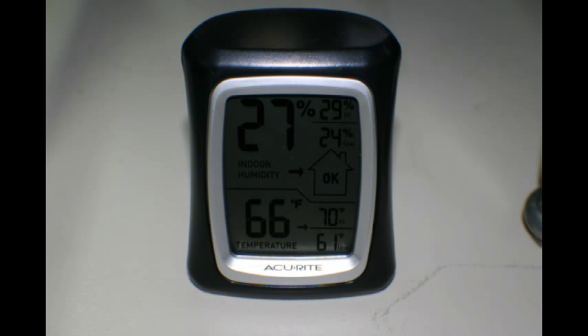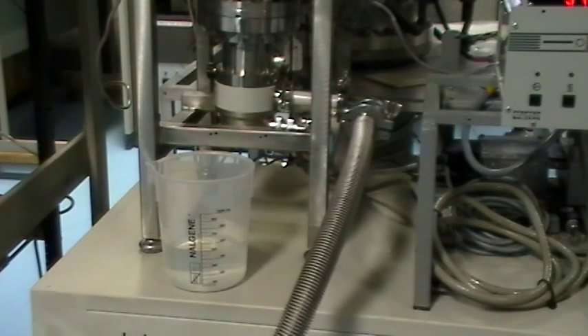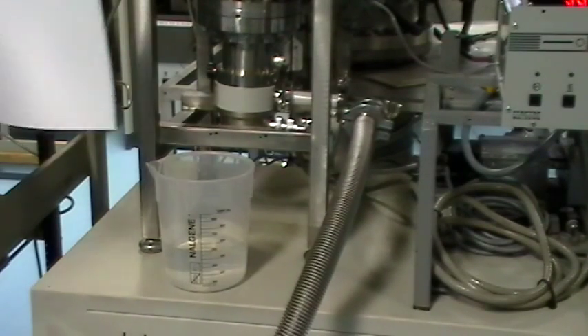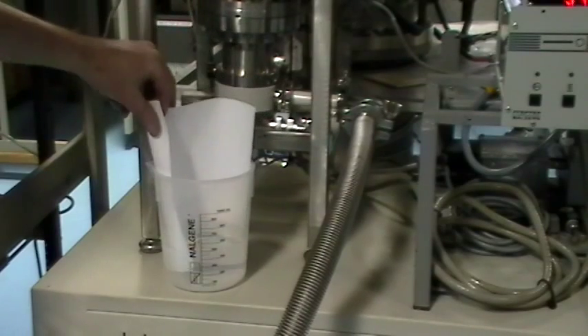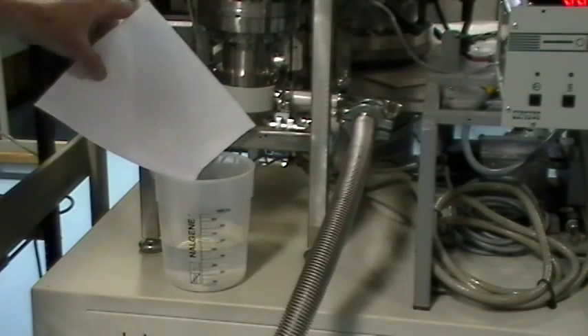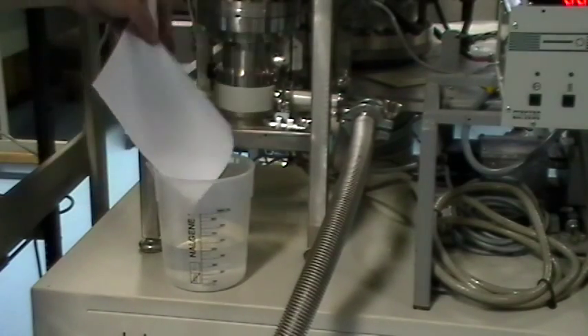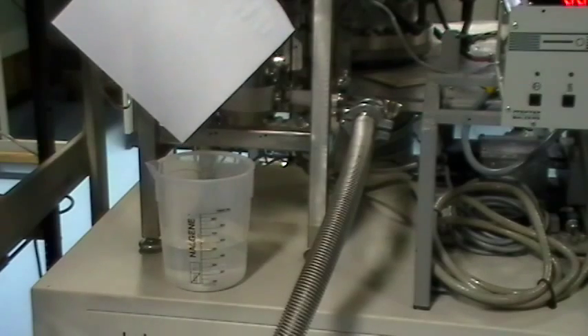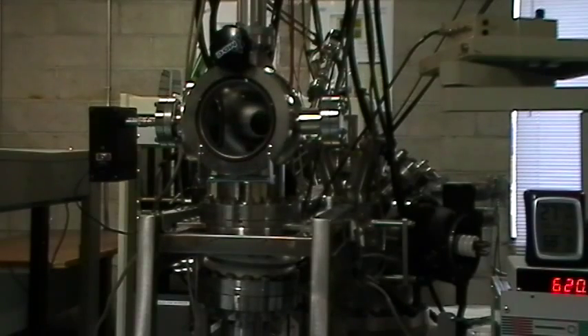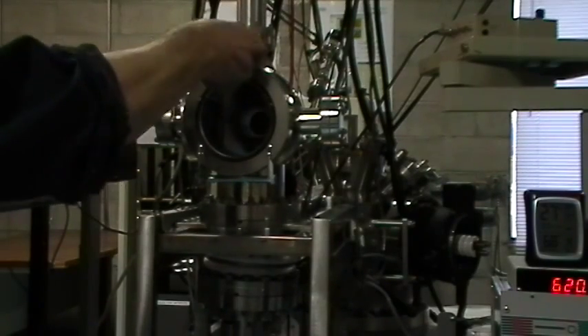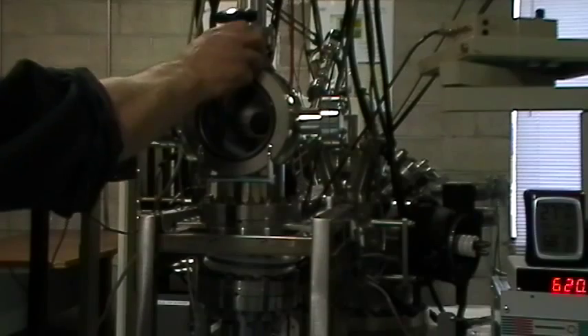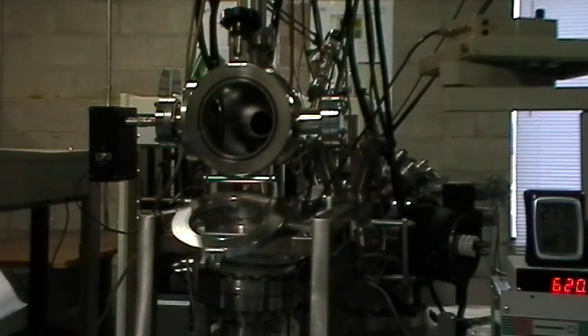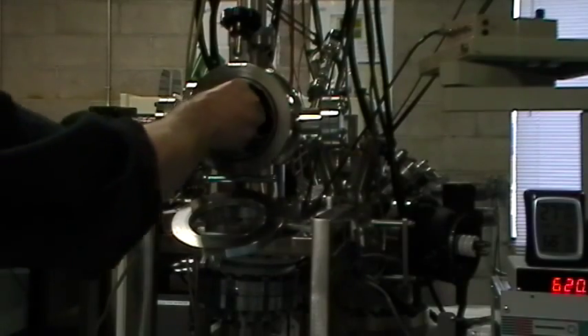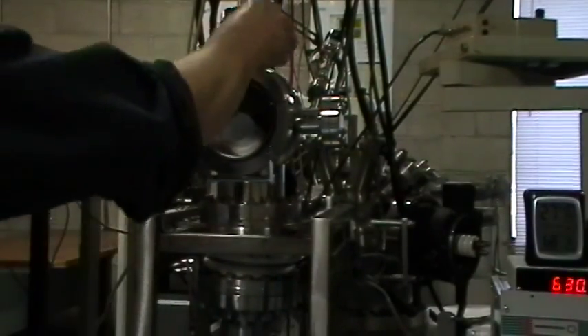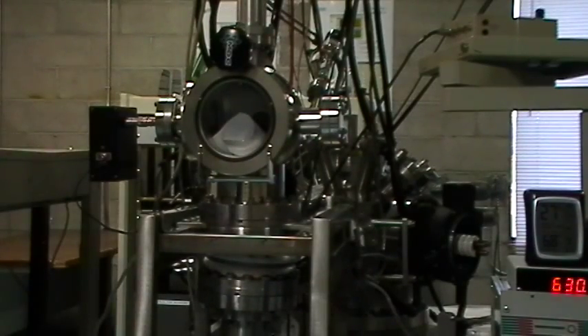It's rather dry here in Bend, Oregon, where we live, and so for the purposes of this test, we had to increase the amount of water vapor in our little test chamber. To do that, we put a small amount of distilled water onto a piece of paper, and we let that soak up for a little bit. Then we carefully fold the paper so that we don't get any water actually on the chamber, that the water is inside of the way we folded it. And we insert it into the chamber, close it back up, and wait for about 30 minutes.